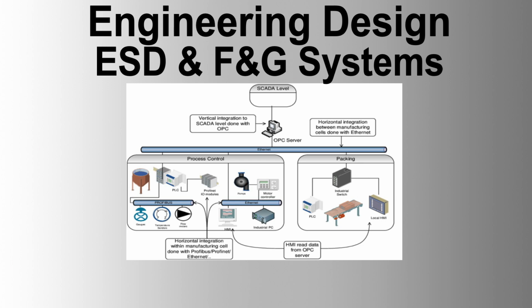Testing scope and procedures. 1. Loop check and functional logic check. Power up the system and conduct a SAT for the system. Loop checks and functional logic checks should be performed to ensure all connections and system logic are functioning correctly. Vendor to assist the fabrication contractor during these checks. 2. Site acceptance test. Vendor to conduct SAT as per the vendor-developed procedure approved by the purchaser.